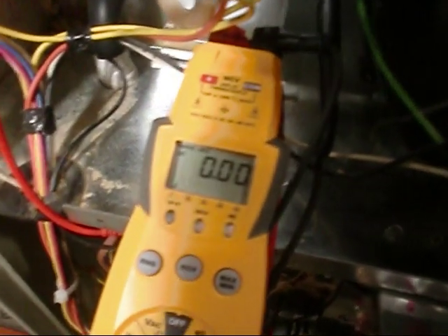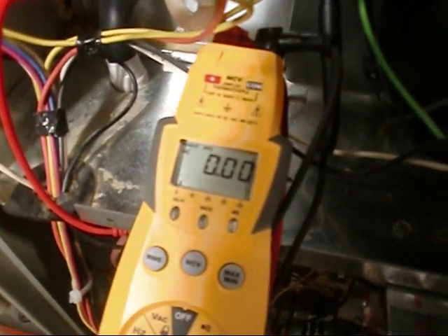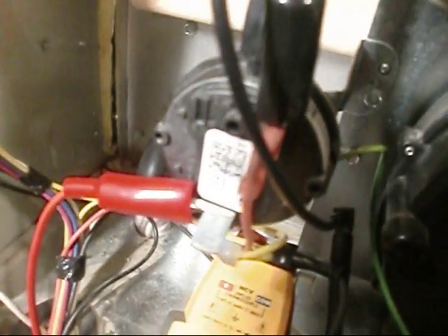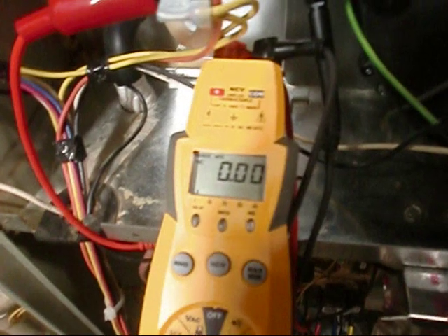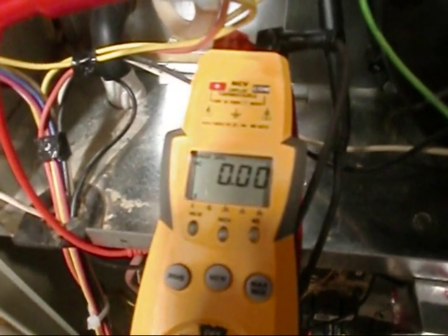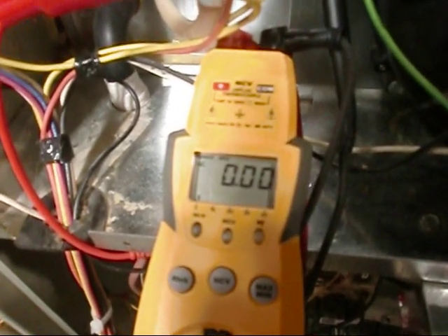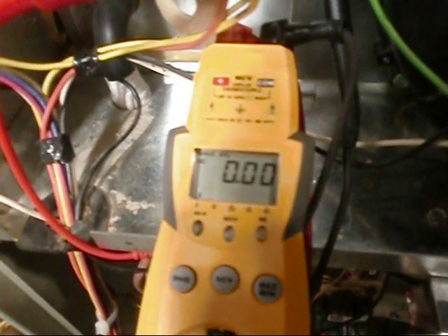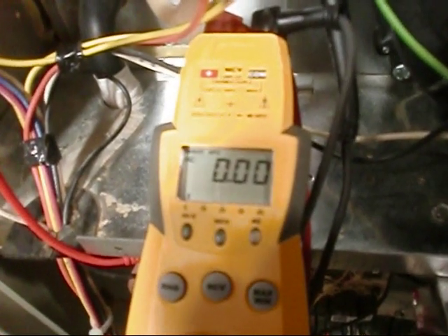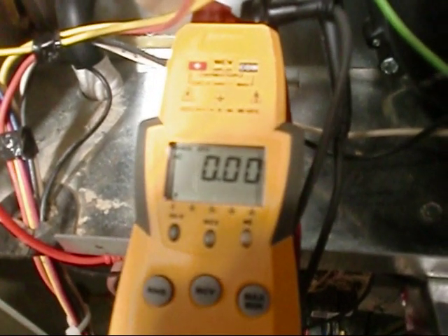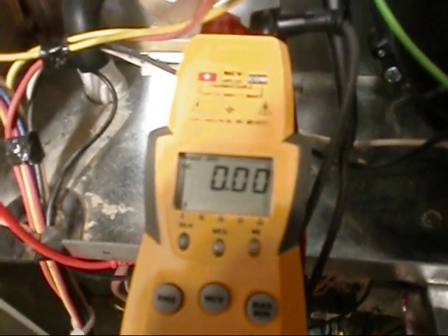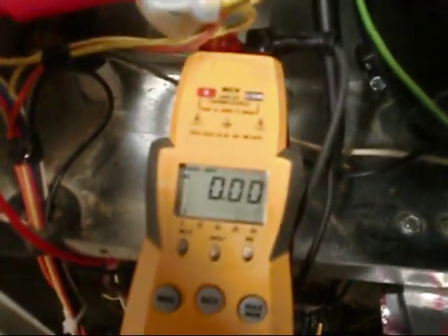We just did that resistance test, and just wanted to show y'all something real quick. I've got spade terminals back on, respective terminals on the pressure switch there. Got the alligator clips hooked to it, and I'm going to go hot here. We should get 24 volts, low voltage, whatnot.